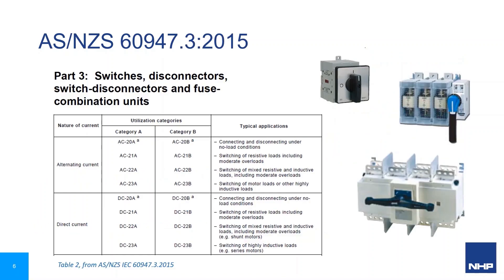The product standard for switch disconnectors, load break switches, and fuse switches is IEC 60947 part 3, and defines their utilisation categories for the switching function of different load types. Category A is for frequent operation, whilst Category B is used where the switching is infrequent or only occasionally required.